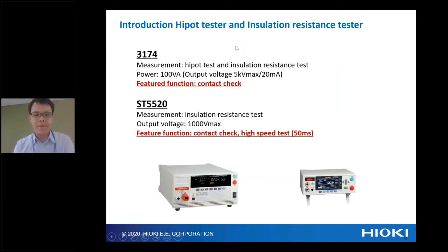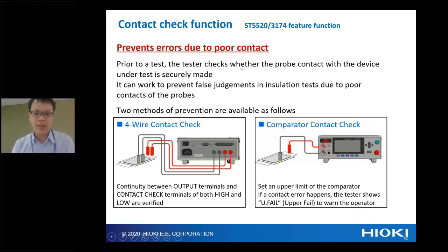And we also have the 3174. This is a little different from these three instruments. It can also do the Hipot test and the insulation resistance test. Power is not so high compared to other products, but it has a contact check function. The ST5520 can do only insulation resistance test. However, it also has a contact check function. So what is the contact check function? It prevents errors due to poor contact. Prior to the test, the tester checks whether the probe contact with the device under test is securely made. It can work to prevent false judgments in the insulation test due to poor contact of the probe.